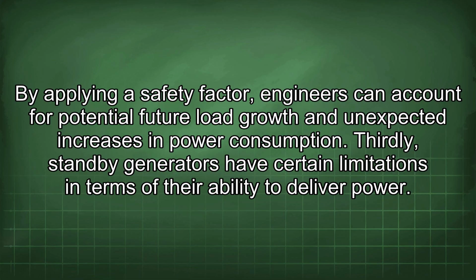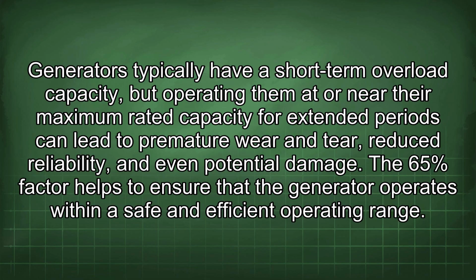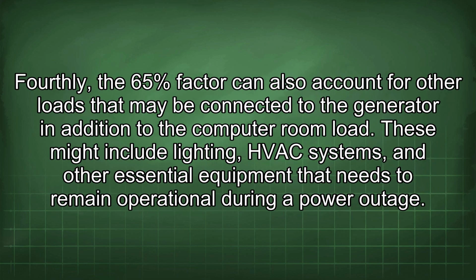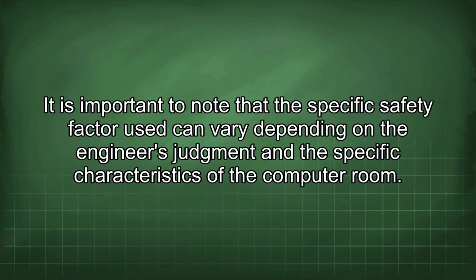Thirdly, standby generators have certain limitations in terms of their ability to deliver power. Generators typically have a short-term overload capacity, but operating them at or near the maximum rated capacity for extended periods can lead to premature wear and tear, reduced reliability, and even potential damage. The 65% factor helps to ensure that the generator operates within a safe and efficient operating range. Fourthly, the 65% factor can also account for other loads that may be connected to the generator in addition to the computer room load. These might include lighting, HVAC systems, and other essential equipment that needs to remain operational during a power outage. It is important to note that the specific safety factor used can vary depending on the engineer's judgment and the specific characteristics of the computer room.